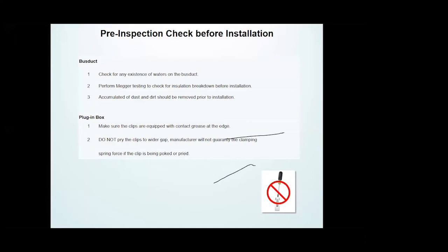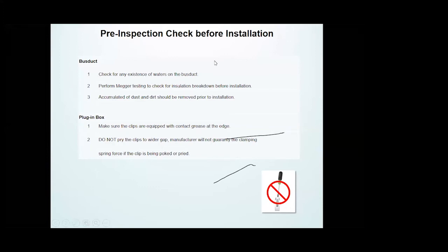This is a pre-inspection check before installation. Before carrying out the installation you must inspect the bus duct and also the plug-in box. For the bus duct there are three things to check: firstly, check for any presence of water on the bus duct; after that, perform megger testing to check for insulation breakdown before installation; then make sure accumulated dust and dirt are removed prior to installation. For the plug-in box, make sure the clips are equipped with contact grease at the edge, and do not pry the clips to widen the gap.